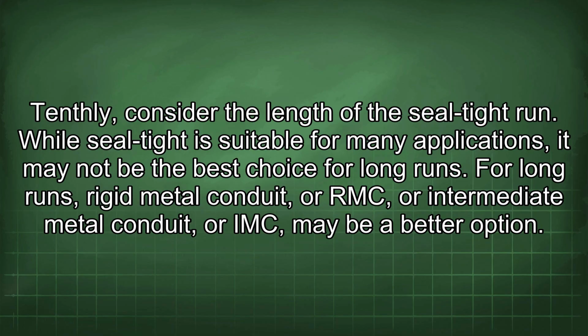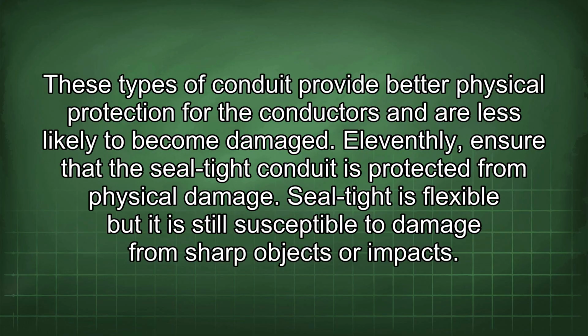Tenthly, consider the length of the seal-tight run. While seal-tight is suitable for many applications, it may not be the best choice for long runs. For long runs, rigid metal conduit, or RMC, or intermediate metal conduit, or IMC, may be a better option. These types of conduit provide better physical protection for the conductors and are less likely to become damaged.